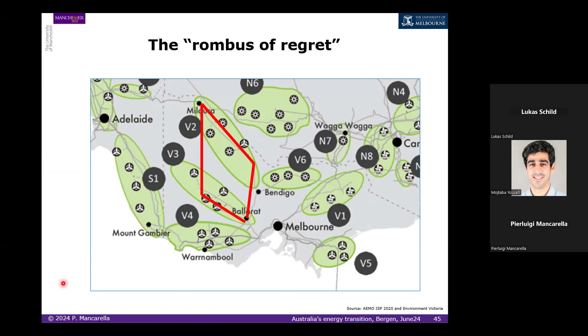There's been lots of research done to understand what's happening here. At the moment, the solution in many cases is instead of having gas turbines running, to use a different type of synchronous machine called synchronous condensers. These are synchronous generators that don't supply active power—they only supply reactive power and can provide other system services. About 3 years ago, once a synchronous condenser entered operation, they could switch off one gas turbine because the condenser alone was enough to provide stability services. This was the first time in the world I saw this kind of operation with renewables, and now there are many more synchronous condensers operating in Australia, with discussions worldwide about doing this.